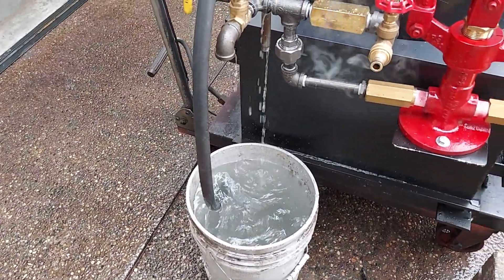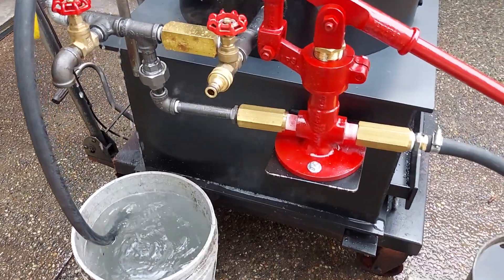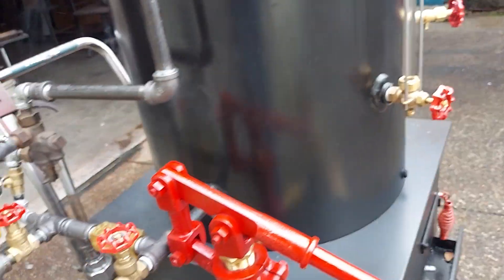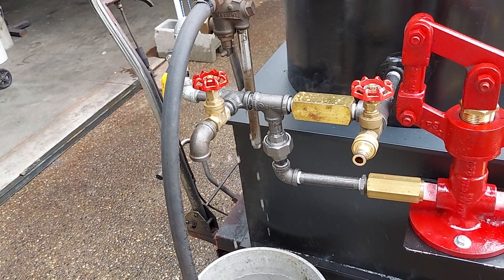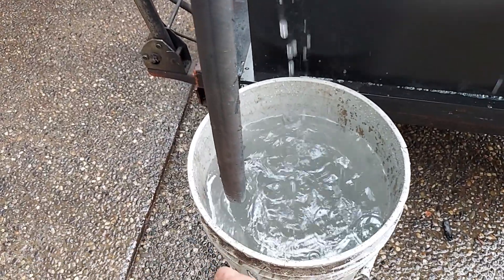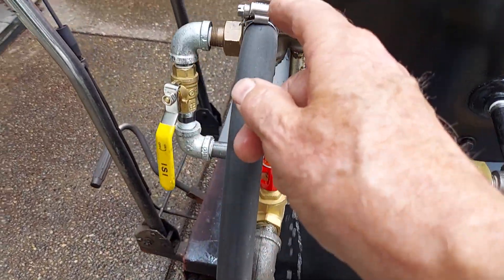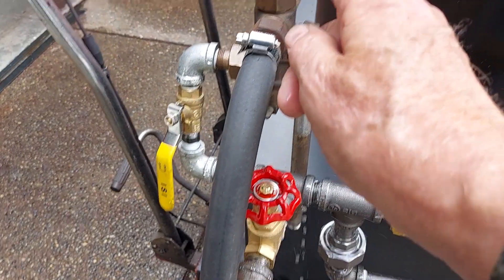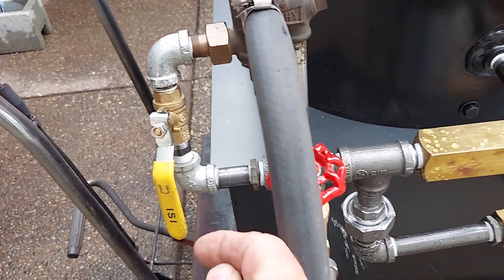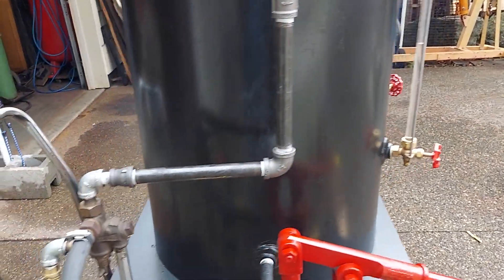Oh, it's working! How about that — it's working! Water's going down in the bucket and it's probably going way up in the sight glass. It seems to go out a lot — that's amazing. The water is coming out of the bucket; it's pulling it up and injecting it — steam coming in here, water coming in here, and it's going out down through the valve and into the boiler. Look at the height of the water now — it's already three quarters; it was halfway up.